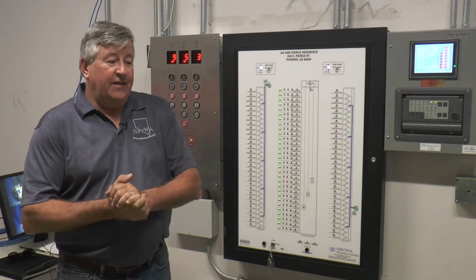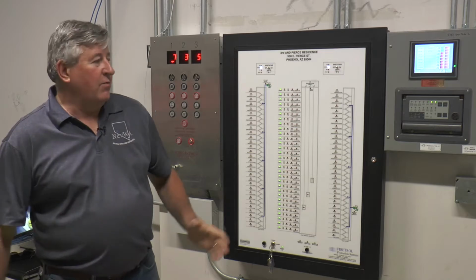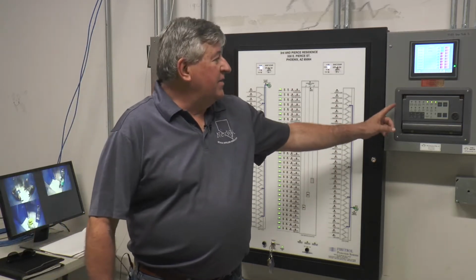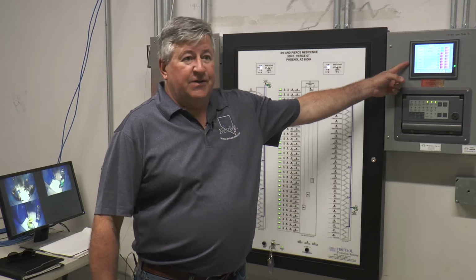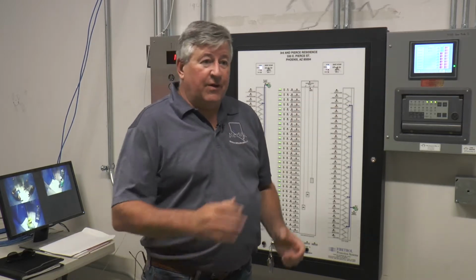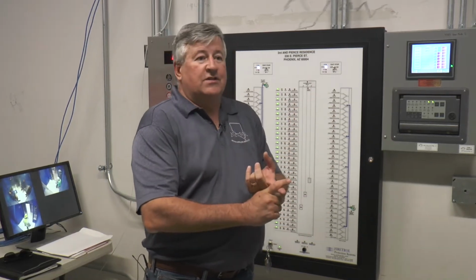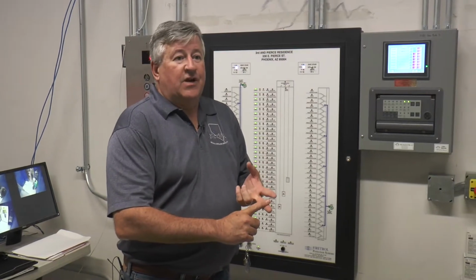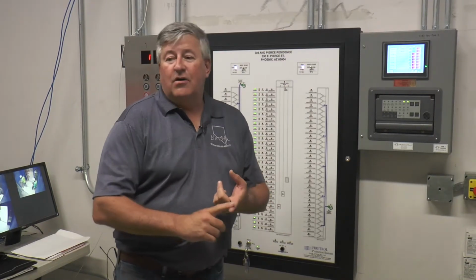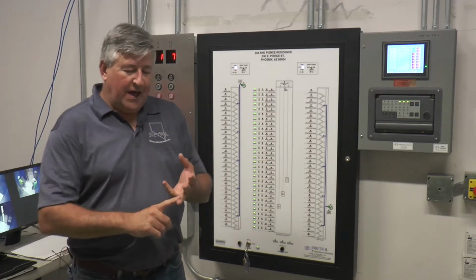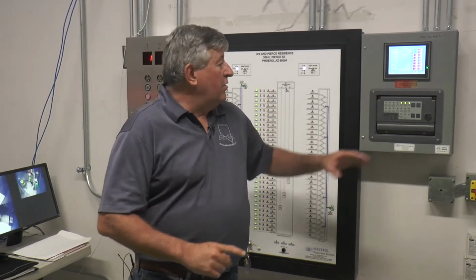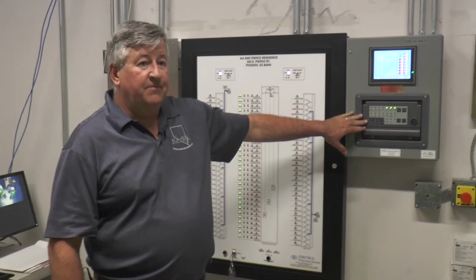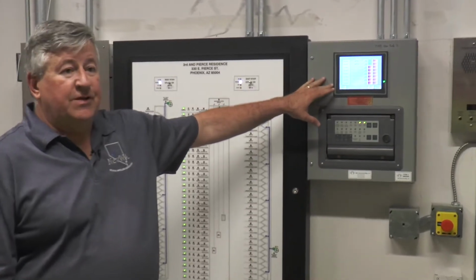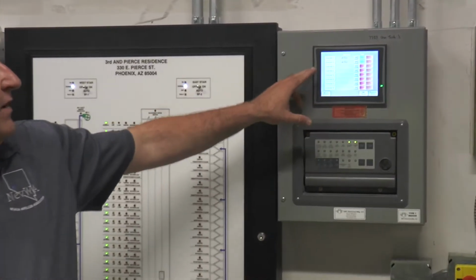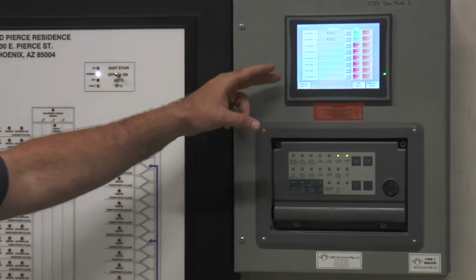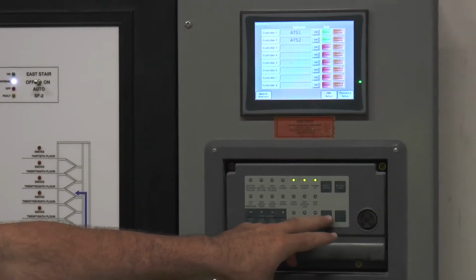We are currently in the fire command room where we provide annunciation for the generator set and the transfer switches. This will be the annunciator that gives you what conditions the generator is in and what state the transfer switch is in. If there's a fault or an alarm, like low fuel, high water temp, or low oil pressure, those alarms will be displayed on this screen. If there's an issue with the transfer switch for position or voltage, it will give you an alarm out here on this display. The display has a test.